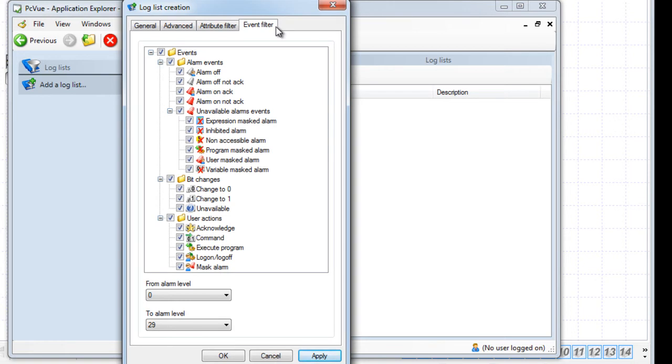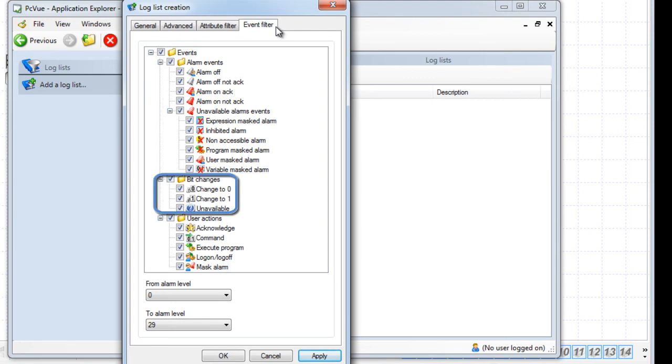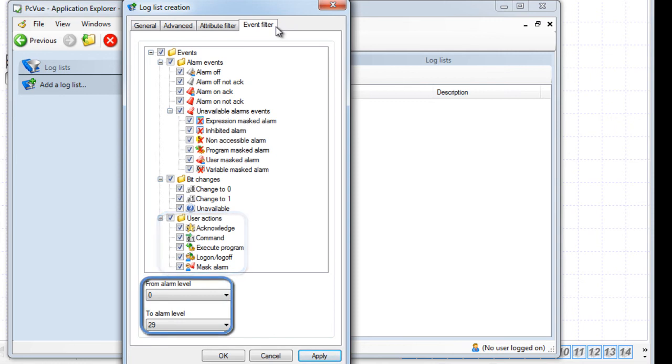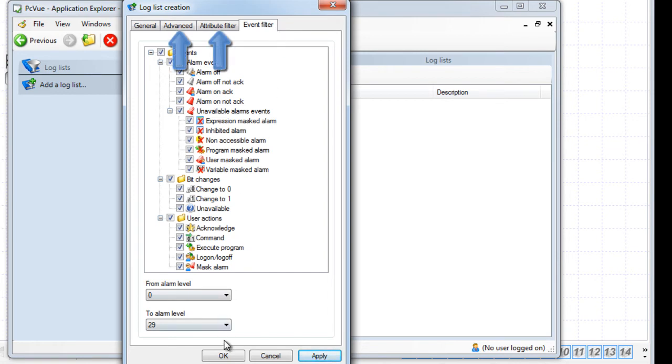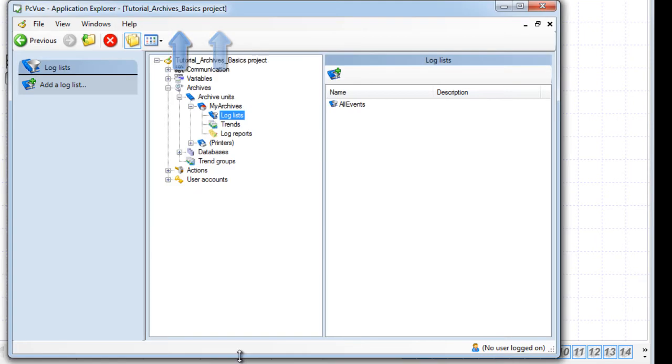The tab Event filter defines the events to be logged with the log list: alarm events, bit changes, and user actions. You can also define the alarm level for the alarm to be logged. Here we left all the events selected. The other two tabs will be discussed in the advanced tutorial. Click OK and the log list is now created.